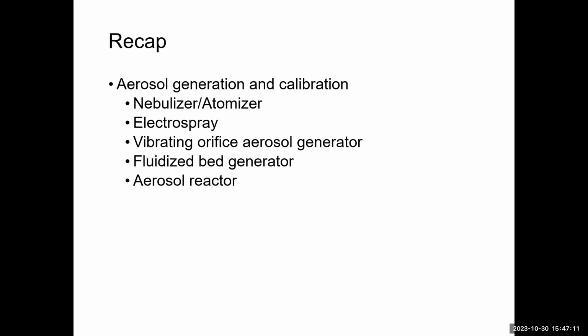Further, we can use these aerosol generation methods to provide aerosols for the calibration of instruments. For example, we said we could use PSL particles, which have very precise control of particle size, to calibrate the DMA, the CPC, or other instruments in order to characterize their size-dependent performance. We could also use the differential mobility analyzer, the DMA, to classify particles of specific sizes and then introduce them into different instruments, right?